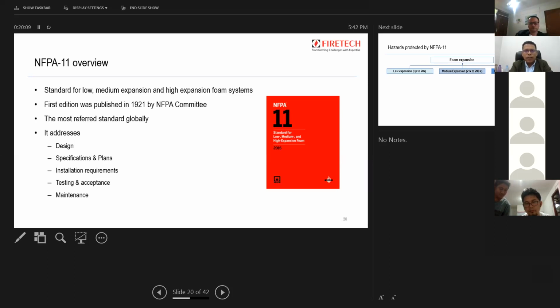So the standard covers low expansion foam systems, medium expansion foam systems, and high expansion foam systems. So what do you mean by expansion? Expansion is basically how much amount of foam solution you are converting into foam. And generally, as mentioned earlier by James, low expansion is up to 20 times of expansion.